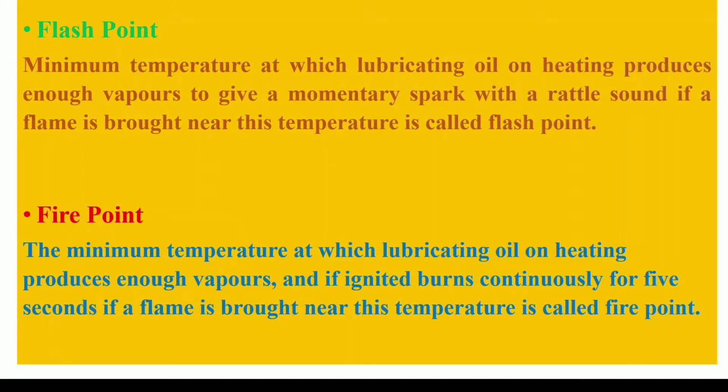Flash point is that minimum temperature at which a lubricating oil under test on heating produces enough vapors to give a momentary spark with a rattle sound if a flame is brought near it.